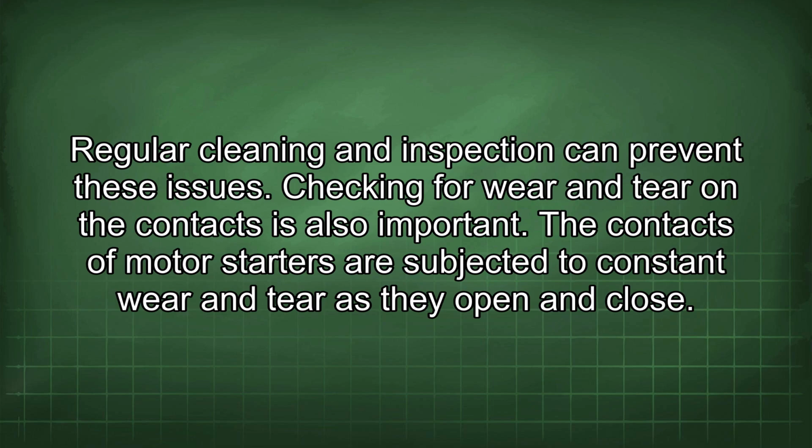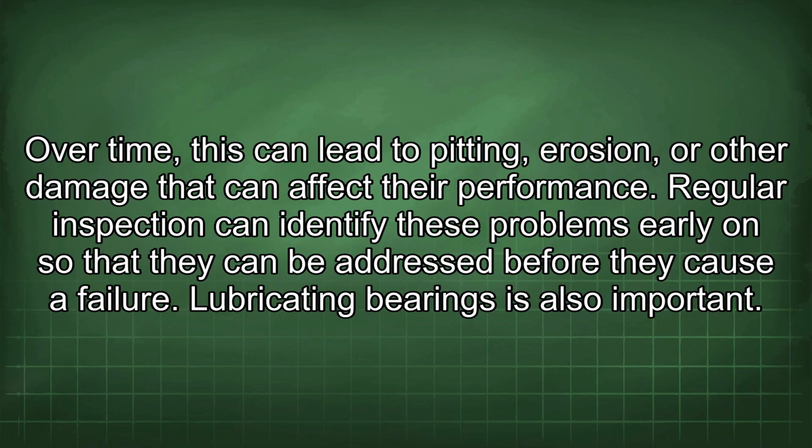Checking for wear and tear on the contacts is also important. The contacts of motor starters are subjected to constant wear and tear as they open and close. Over time, this can lead to pitting, erosion, or other damage that can affect their performance. Regular inspection can identify these problems early on so that they can be addressed before they cause a failure.